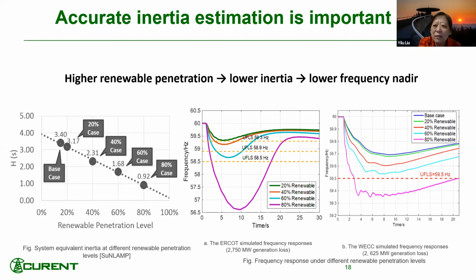Right now we have several versions. The majority of them we deployed are sampling at 1440, which means 1440 samples per second, or 24 points per cycle. We output data at only 10 points per second because the frequency we're dealing with is an electromechanical system, so frequencies aren't supposed to jump real wild. We could output all of them, but we don't, otherwise we'd run into the next problem, which is storage.